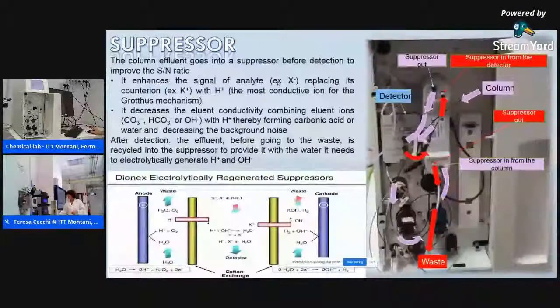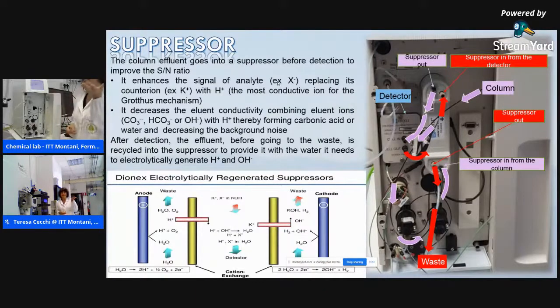What is suppression? What is a suppressor? A suppressor is a device which increases the signal of anionic analytes and decreases the signal from the background noise. How does it work? A suppressor usually electrolyzes water to produce H+ and OH-. In this way, if we are in the anionic configuration, we have a lot of OH- hydroxyl ions in the effluent, which are highly conductive.